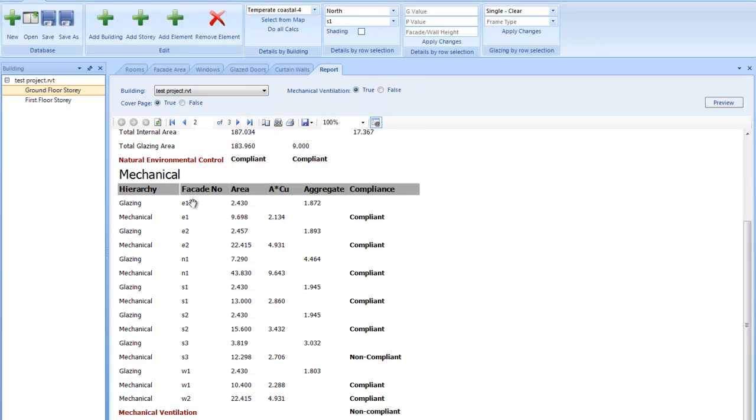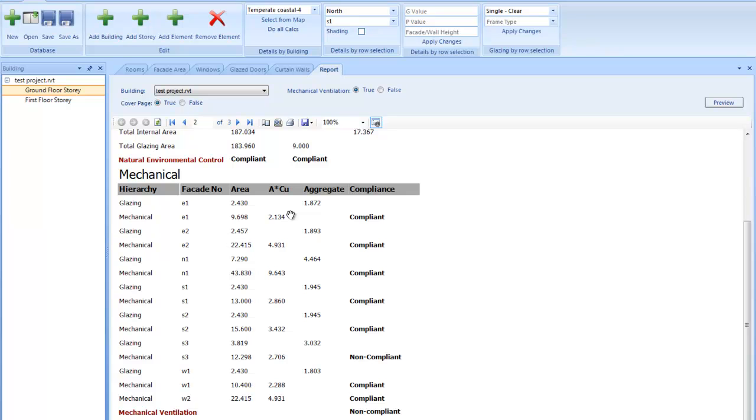And this is per facade. So the bottom values here is your mechanical allowance aggregate. And the glazing that you have on that facade, that's the aggregate energy value. And again, if that's lower than the allowable, then it's compliant. Same in this case. Here at the bottom, this one exceeds the allowable, so that's non-compliant. And that creates a non-compliant mechanical report. So if any one of these fails, then the whole mechanical ventilation is non-compliant.